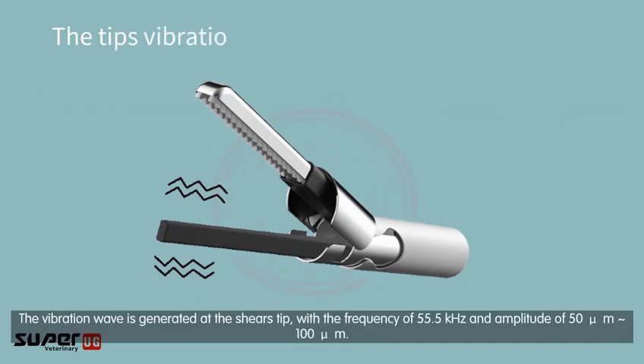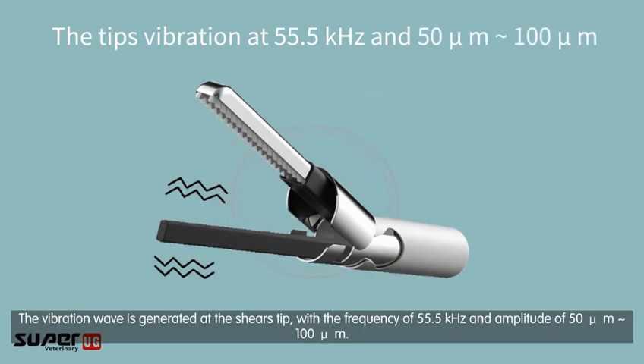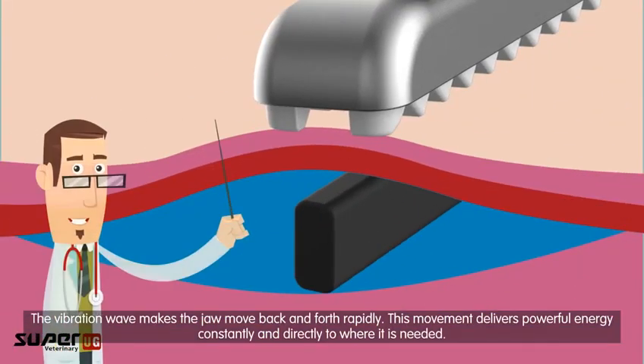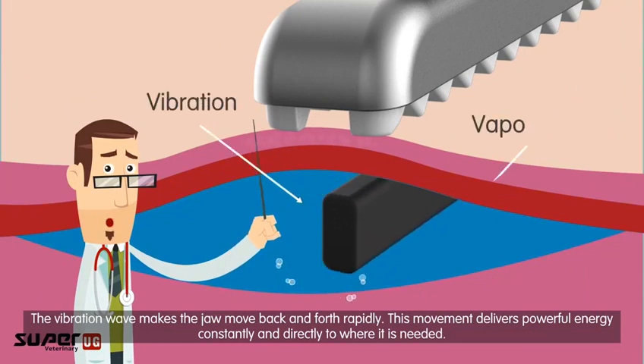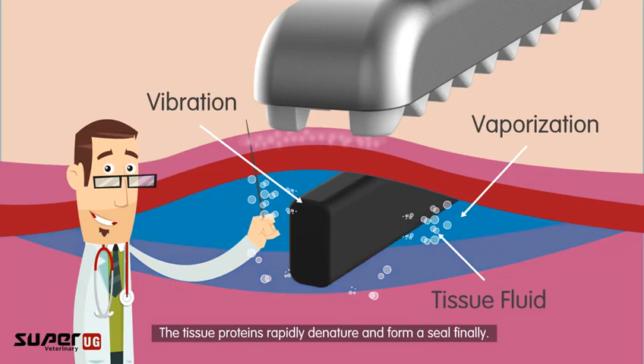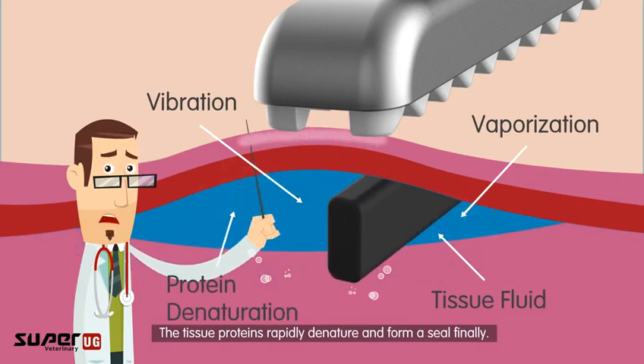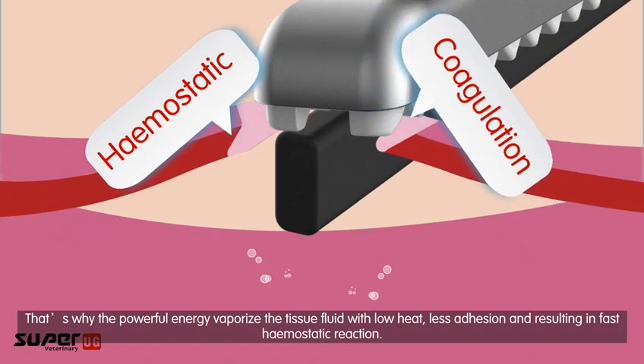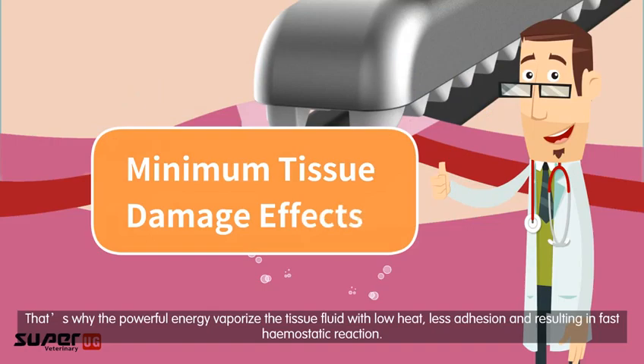The vibration wave is generated at the shear's tip, with a frequency of 55.5 kHz and an amplitude of 50 to 100 microns. This vibration makes the jaw move back and forth rapidly, delivering powerful energy constantly and directly to where it is needed. The tissue proteins rapidly denature and form a seal, which is why the energy vaporizes tissue with low heat, less adhesion, and results in fast hemostatic reactions.